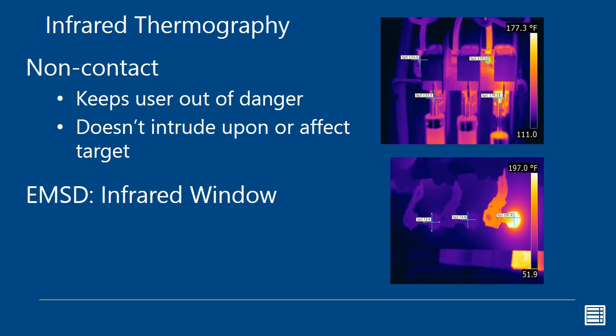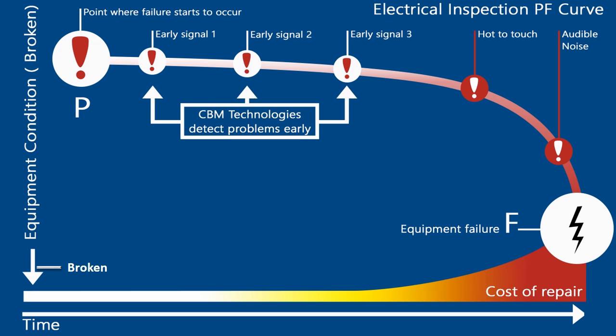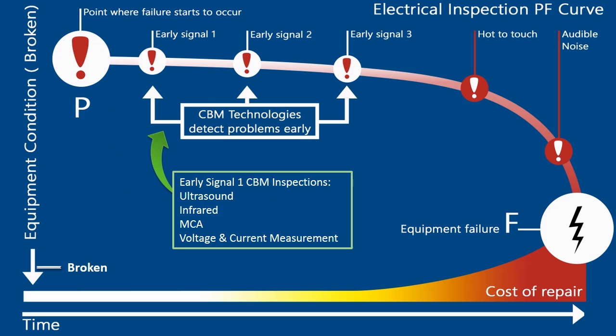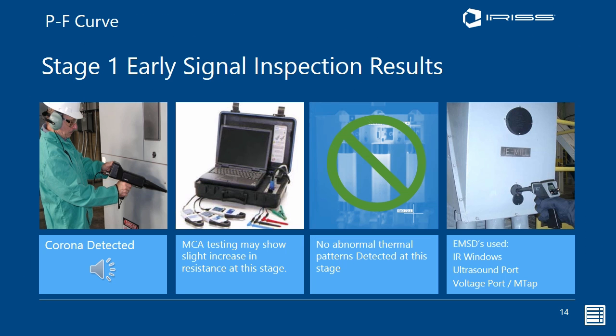So when we're looking at the PF curve and the early signals, when we look at the equipment we're using, we may hear corona depending on the voltage, and this is more to do with above 3 kilovolts. You might hear corona, and corona sounds like this. The motor current analysis or current measurement might start to show signs of resistance at this stage. Infrared may not pick up any thermal patterns at this early stage. Obviously the EMSDs we'll be using will be the full range, using IR windows, ultrasound ports and voltage ports.